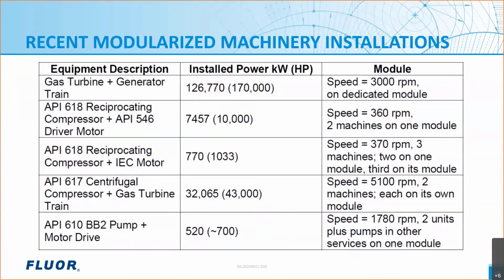As shown on this slide, different types of rotating equipment with small to very large installed power are mounted on transportable structural steel modules. Pumps represent about 80% of rotating equipment in most process facilities. In addition to the BB2 type included in the table, Fluor has also modularized API 610 type OH2, OH3, BB3, and ASME B73.1 pumps and motors, including adjustable frequency drives in various services on hydrocarbon processing and oil and gas projects.